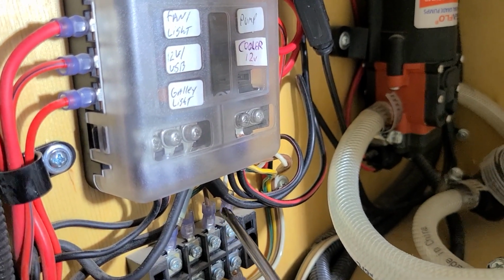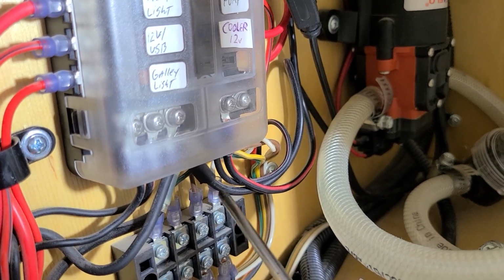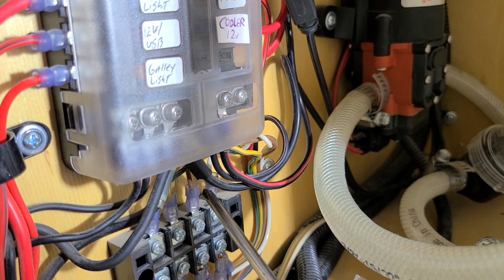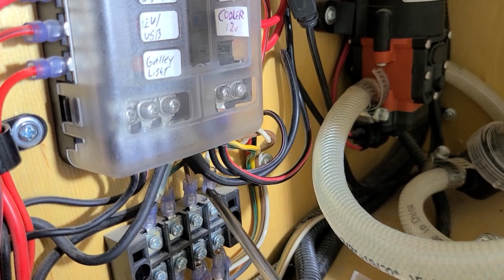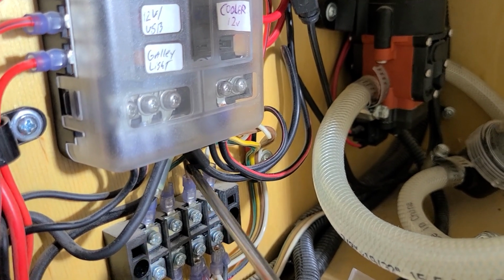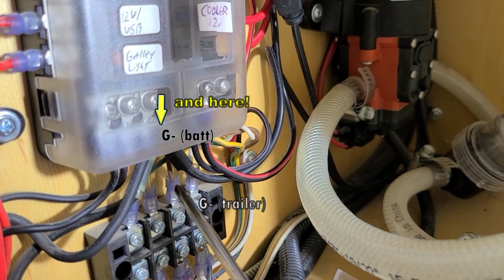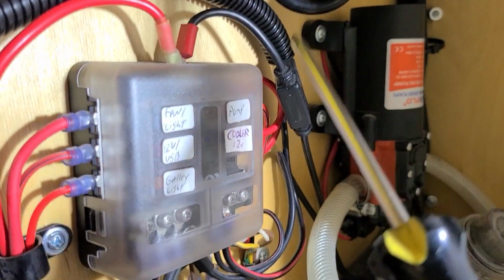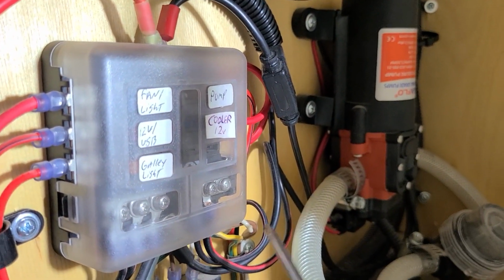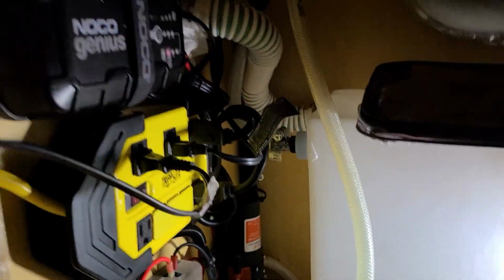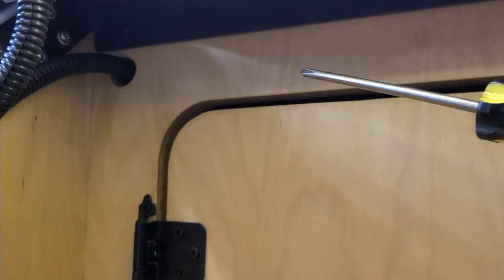And that would also show by doing the multimeter test that I just demonstrated. That would show that even if your brown wire was disconnected here, if you probe the brown wire to your ground, it would show that happening, because it would be coming through the box into the wire somewhere over here. The wire goes back behind the cabinets here in the galley and then comes up here and whatnot. So there's a chance that there's a splice somewhere in there, and that's what that would tell you.